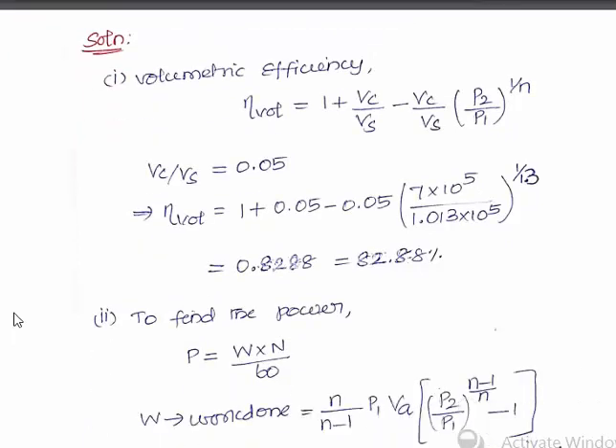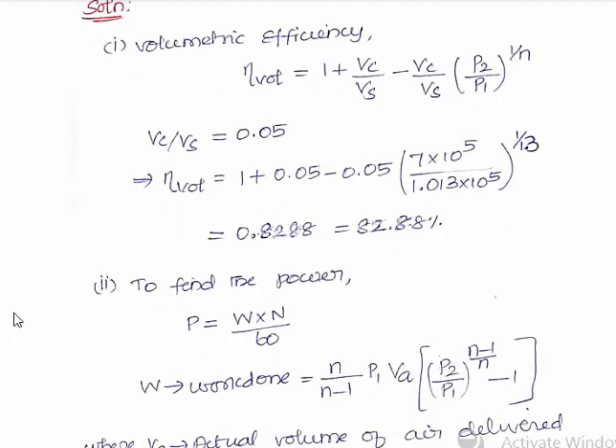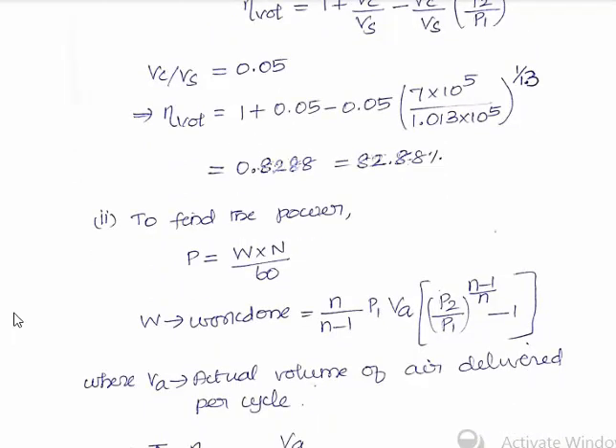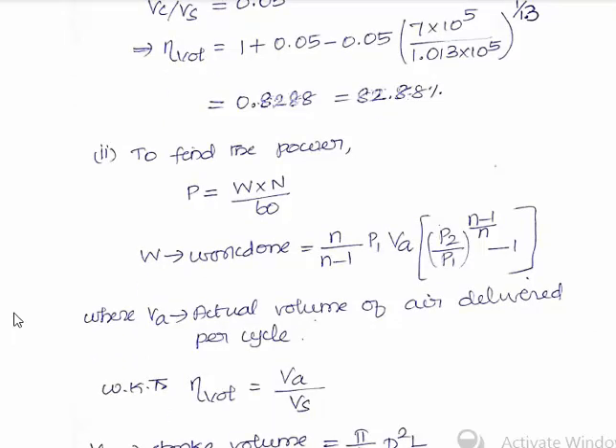The second part is to calculate the power supplied to the compressor. The power output formula for a single-acting single-stage compressor is P = W × N/60, where N is the speed. The work done W for a polytropic process is: W = [n/(n−1)] × P1 × VA × [(P2/P1)^((n−1)/n) − 1]. Here VA is the actual volume of air delivered per cycle, found using volumetric efficiency = VA/VS.